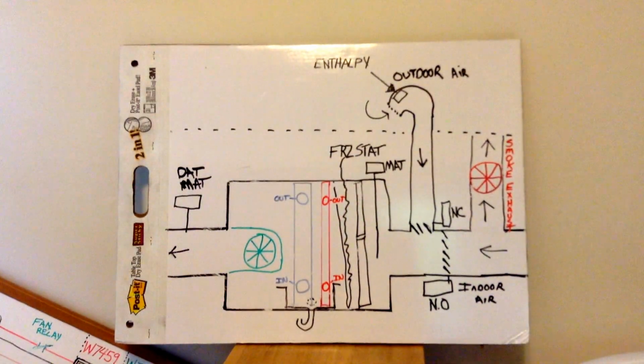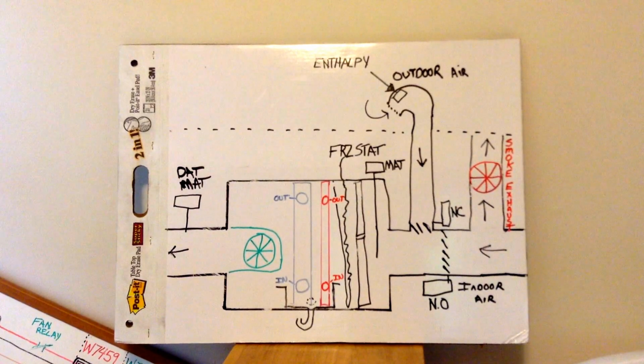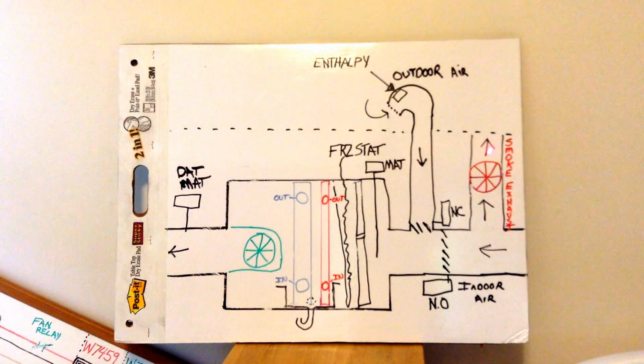The other thing that gets a little complicated on these, and I'll talk about later, is you see here on this one I've got smoke exhaust. On some malls, the mall is tied in to the unit partially in a fire mode. This blower will come on when there's a fire. It'll shut these dampers and shut these dampers. Sometimes it'll have an extra set of dampers here possibly, and they'll actually use this blower to suck smoke out of the store and blow it up on the roof.